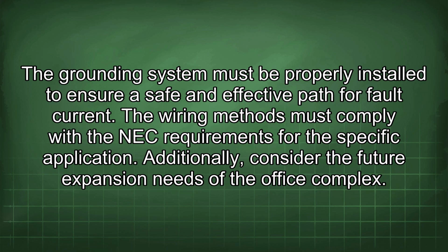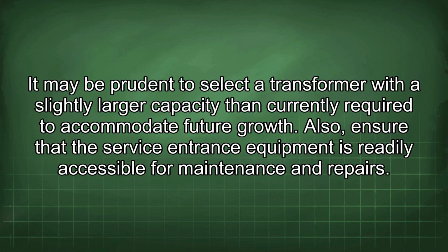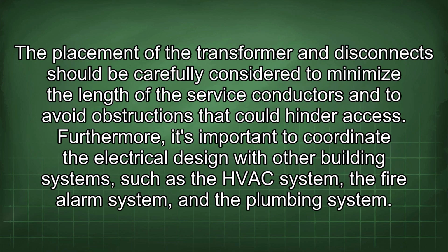Additionally, consider the future expansion needs of the office complex. It may be prudent to select a transformer with a slightly larger capacity than currently required to accommodate future growth. Also, ensure that the service entrance equipment is readily accessible for maintenance and repairs. The placement of the transformer and disconnect should be carefully considered to minimize the length of the service conductors and to avoid obstructions that could hinder access.